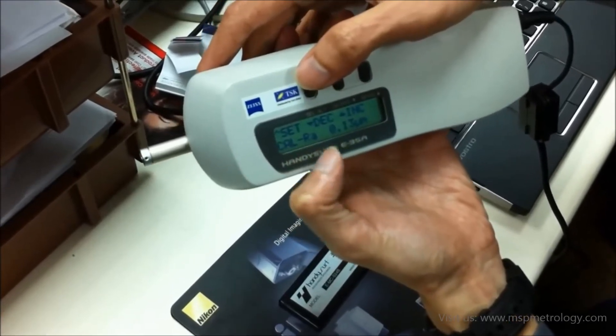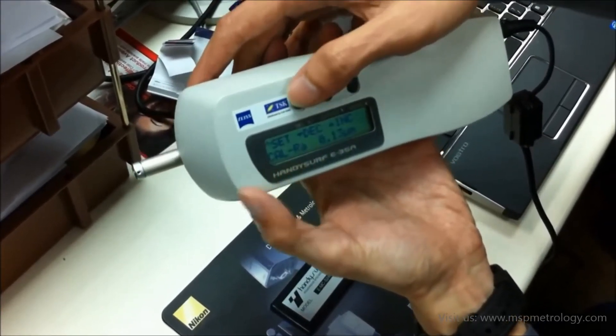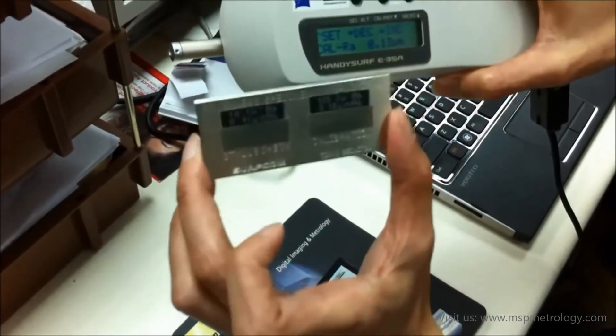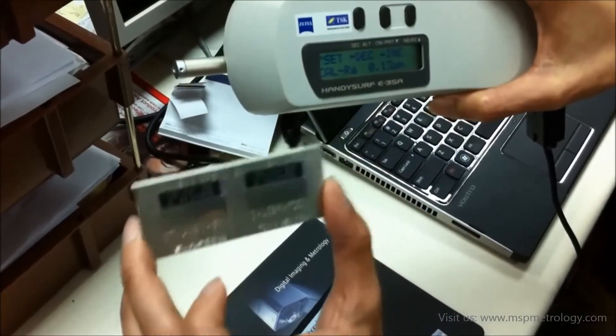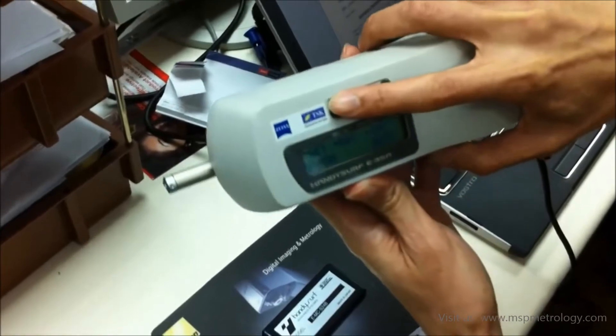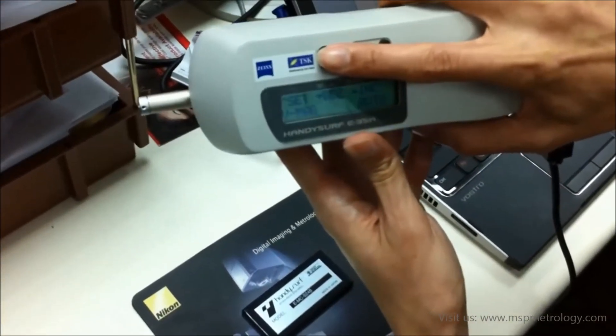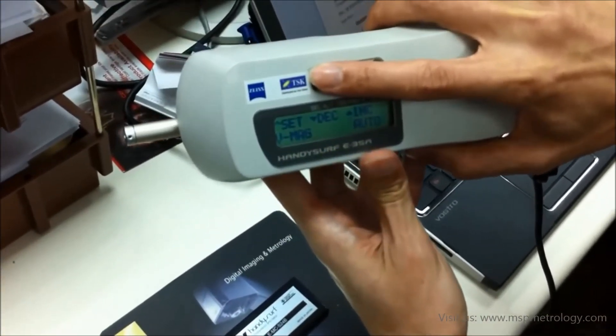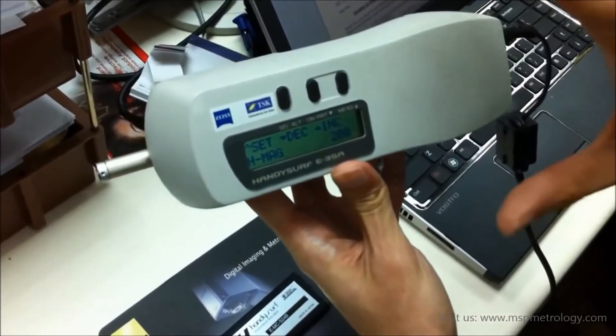You can do a calibration using this method. There's also a calibration test specimen here. If the instrument is not accurate, you calibrate it against the specimen. You can also do magnification, vertical and horizontal, to magnify areas that are too small to see.